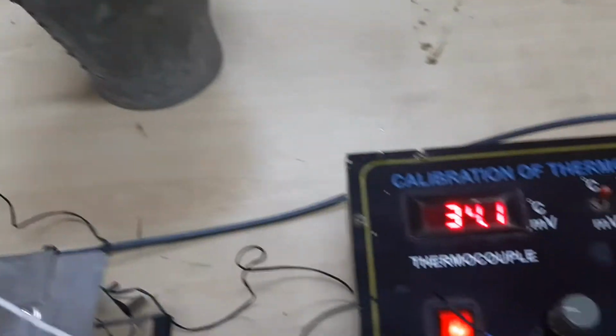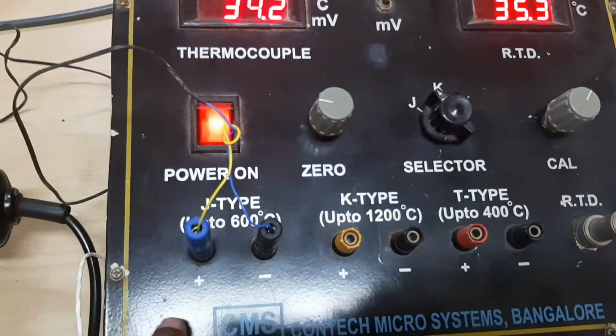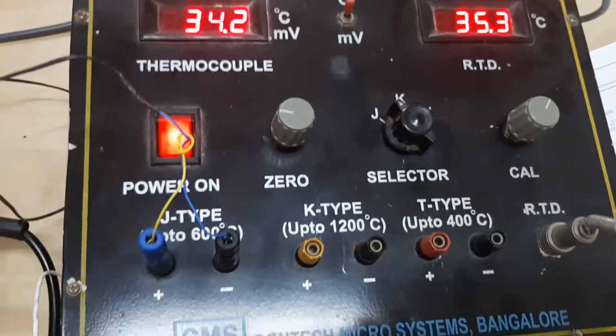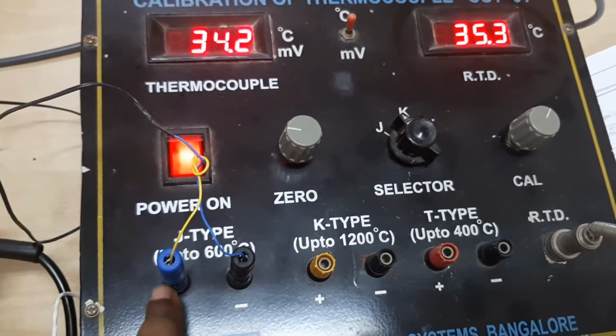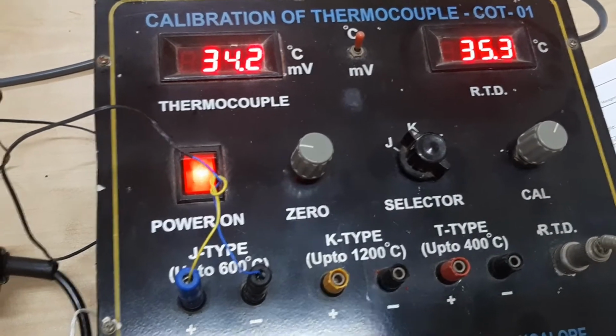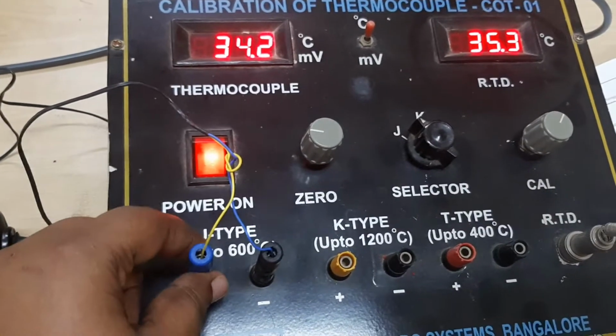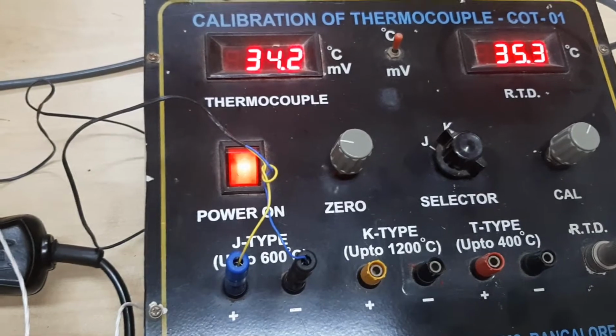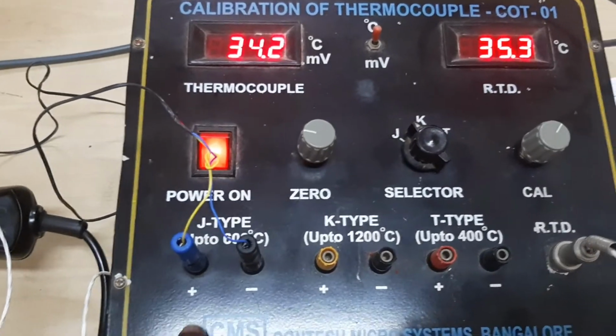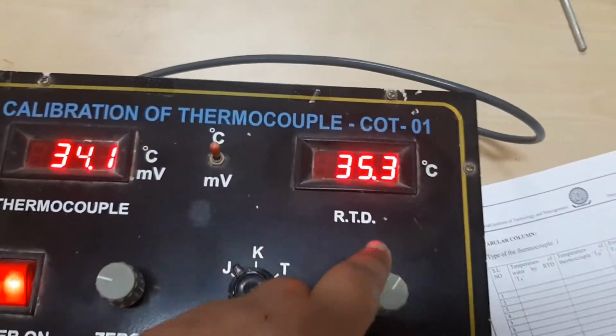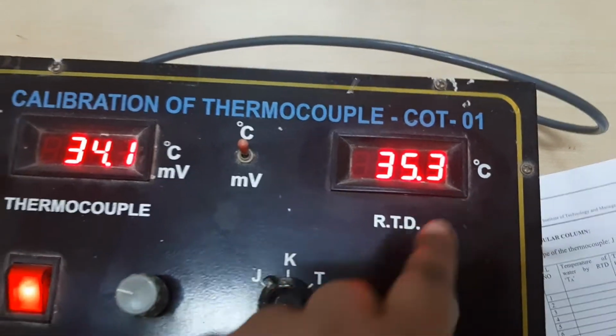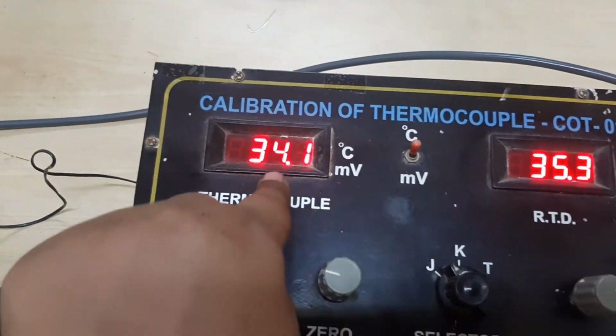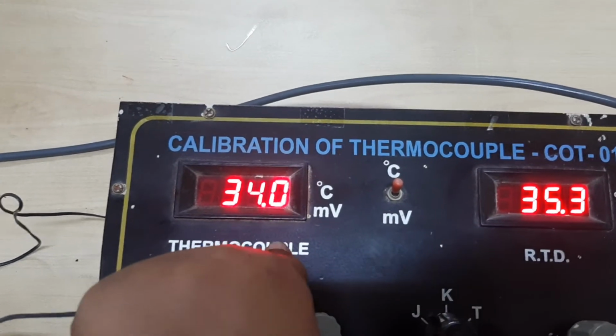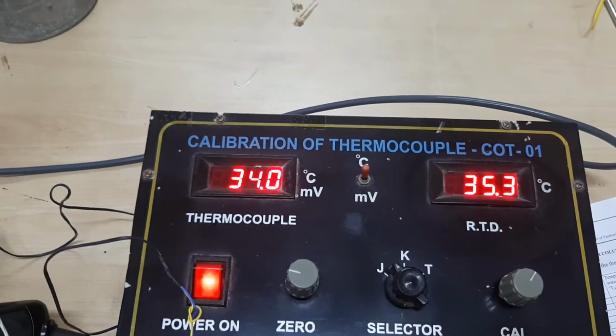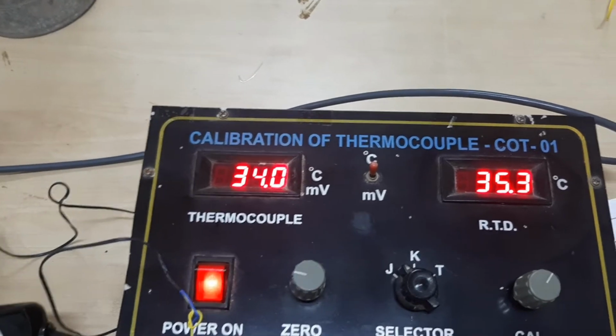Based on the material used, a thermocouple of the J type material is manufactured and connected to the circuit using two color codes, indicated here as blue and black. One indicates negative and the other positive. You insert them here and make the connections, right? The first step in the calibration process is, when the RTD is showing 35.3, to use the zero knob to set your thermocouple value also to 35.3. A small variation of plus or minus 1 degree is fair enough.